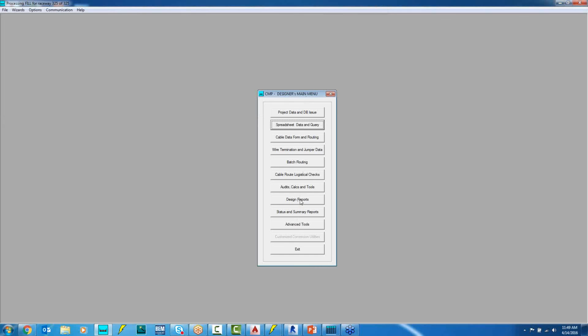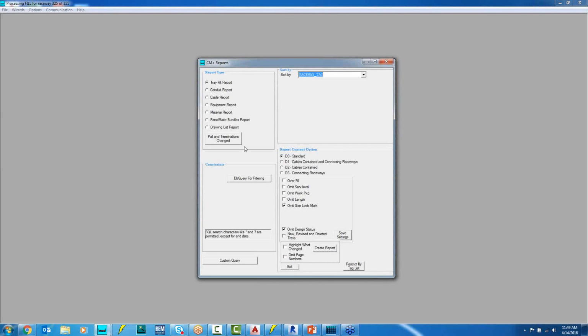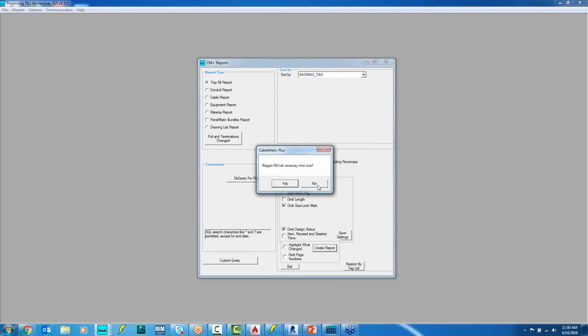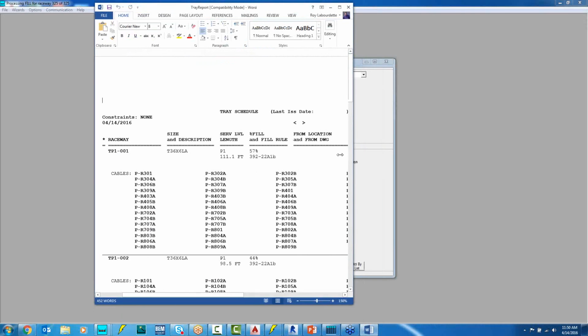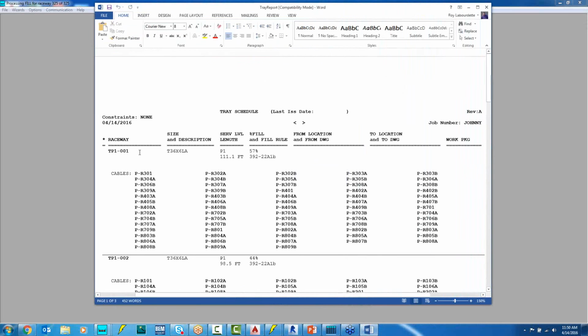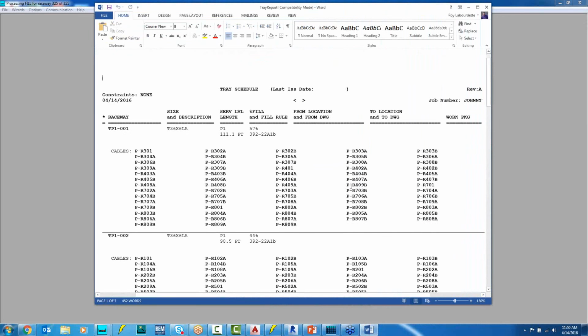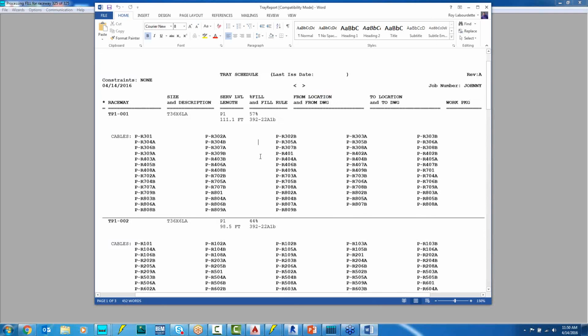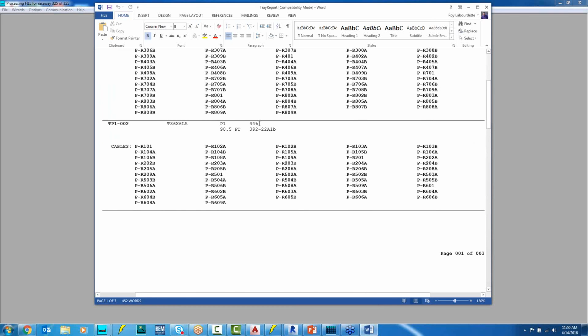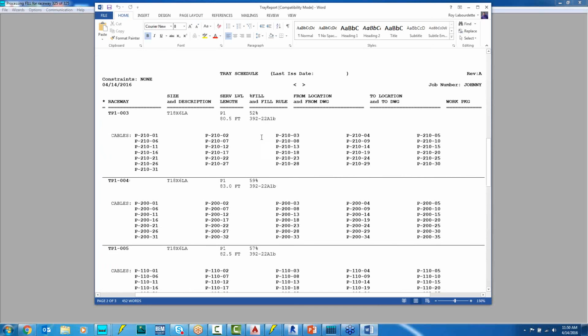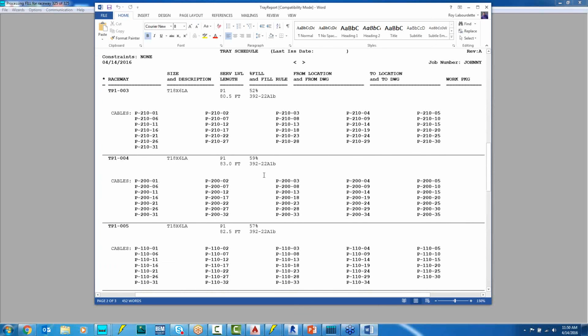I can now go to my design reports and get my tray fill report with a list of the cables and create that report. It's asking me if I want to resize those raceways, and I'm going to say no. So the program will then tell me that the 6 raceways, this is TP001, contains all of these cables, and it is 57% full based on this section of the National Electrical Code. And as you can see, other cable trays are at various percentages of fill. We've set our limit at 80%.